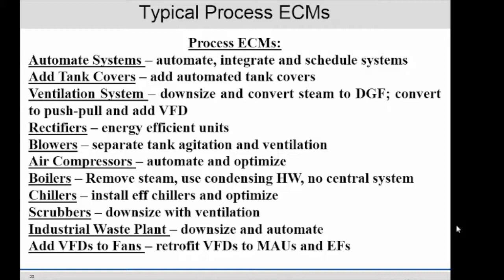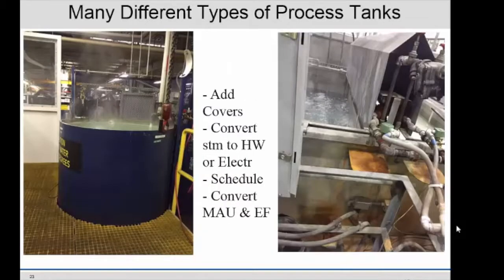VFDs, we put VFDs on the makeup air units and the exhaust fans. We convert the steam, usually to natural gas firing. And I'm going to show you in a minute why, because steam costs a lot. Besides being very wasteful, it costs a lot of money. I'll show you that in a minute.